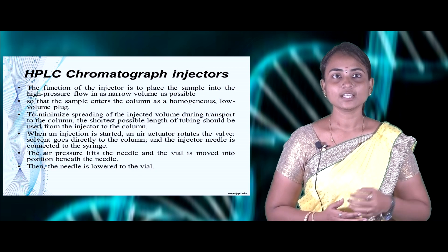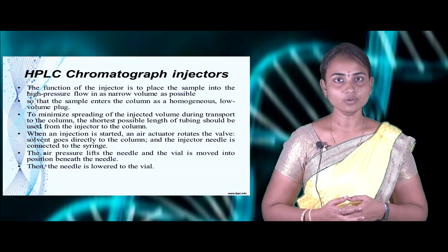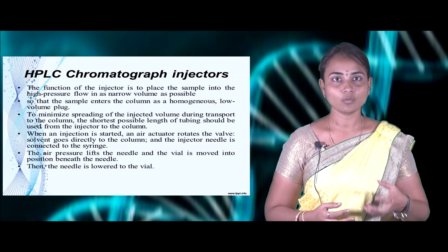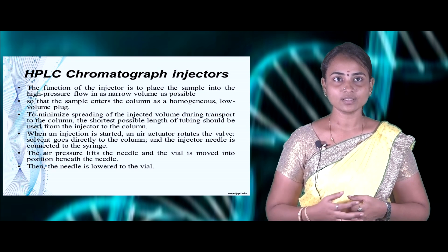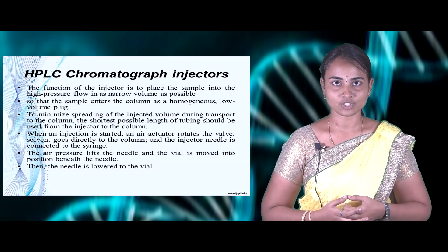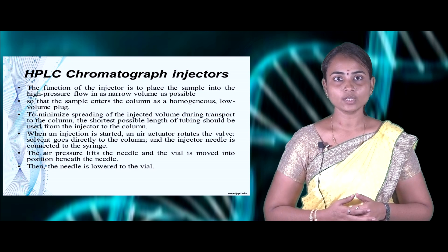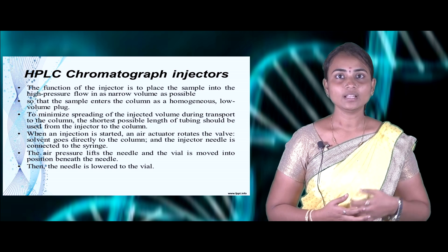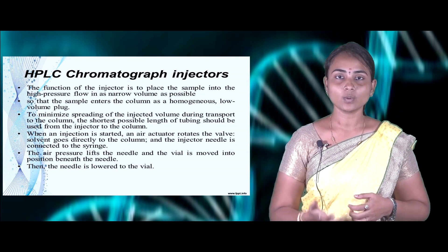Coming to the HPLC injector: the main function of the injector involves separating different samples and pushing them into the column through high pressure at a narrow volume, where the sample enters as a homogeneous, low-volume plug. To minimize spreading of the sample volume during transport into the column, the shortest possible length of tubing should be used. When injection starts, an air actuator rotates the valve while solvent goes directly to the column; the injector needle connected to a syringe is then lowered into the vial to aspirate the sample.